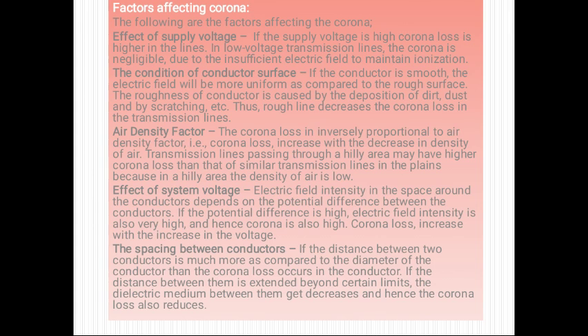Now there are some factors which affect corona loss. First is the effect of supply voltage. How does supply voltage affect the corona? If the supply voltage is higher, corona loss is higher. In a low voltage transmission line, the corona is negligible due to insufficient electric field to maintain ionization. It means in a high voltage line, the electric field around the conductor becomes higher, due to which ionization of particles surrounding the conductor forms an arc or hissing noise.